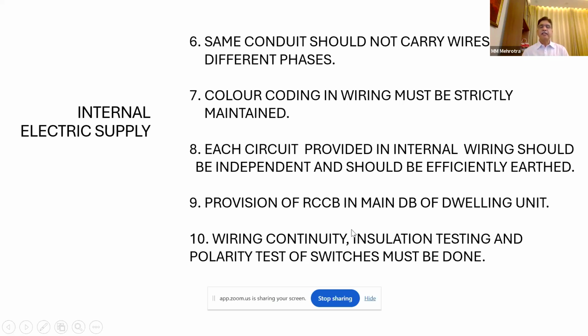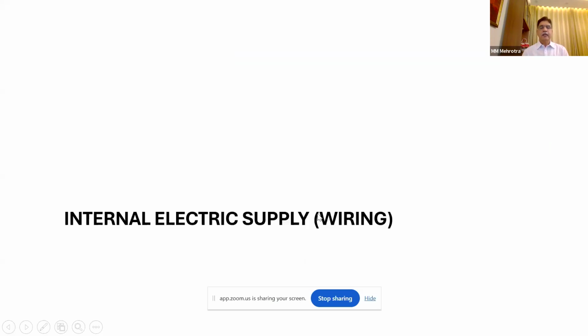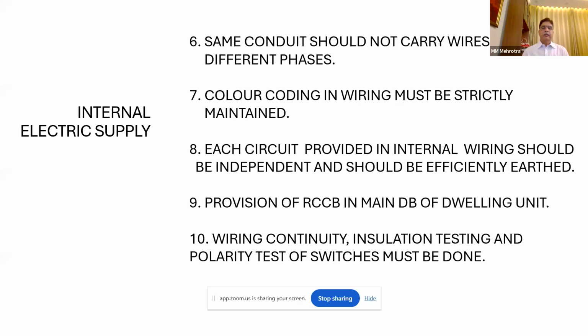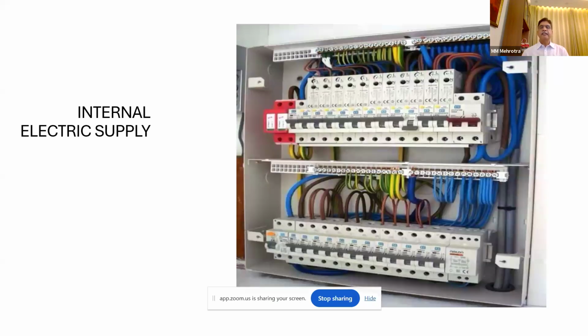Now RCCB is very common. It's an important safety gadget, a residual current circuit breaker, so that you don't get any shock. Wire continuity, polarity. What is polarity? It means the switch should be placed in the phase wire, not in the neutral wire. Now this is a neat method of connecting my circuits. It should not be a bunch. It should be neat. Each circuit should be separate.